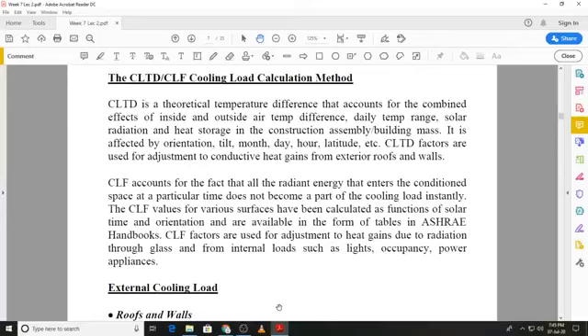So you can have different types of constructions, and when we have a different type of construction, it also affects the amount of heat that is stored in that structure, and that will also affect the rate of heat transfer through that surface. So if we want to take into account all these variables and still use an equation like we had in the case of heat transfer, that is Q equal to UA delta T, we cannot use delta T. Instead, we replace delta T by CLTD.